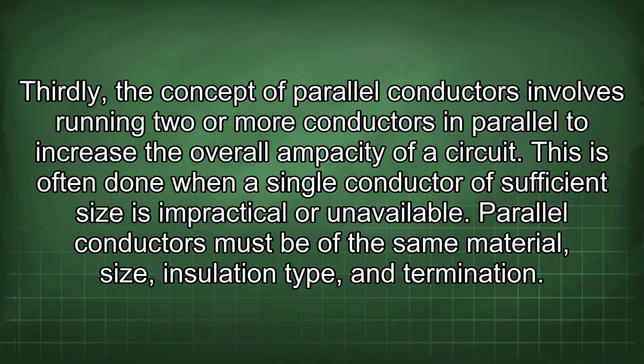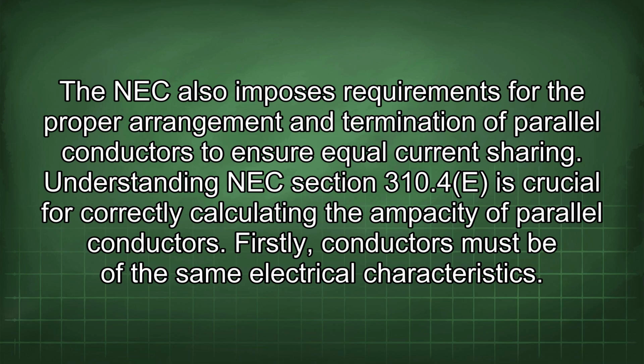Thirdly, the concept of parallel conductors involves running two or more conductors in parallel to increase the overall ampacity of a circuit. This is often done when a single conductor of sufficient size is impractical or unavailable. Parallel conductors must be of the same material, size, insulation type, and termination. The NEC also imposes requirements for the proper arrangement and termination of parallel conductors to ensure equal current sharing.